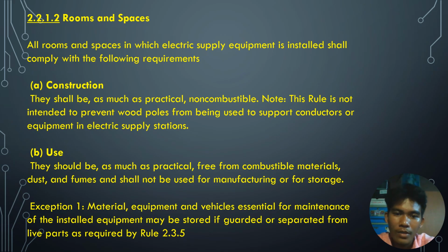So it means that they should be using non-combustible materials like metals, but it is not intended to stop using wood poles to support conductors. Use: they should be, as much as practical, free from combustible materials, dust and fumes, and shall not be used for manufacturing or for storage. Exception: materials, equipment, and vehicles essential for maintenance of the installation equipment may be stored if guarded or separated from live parts as required by Rule 2.3.5.